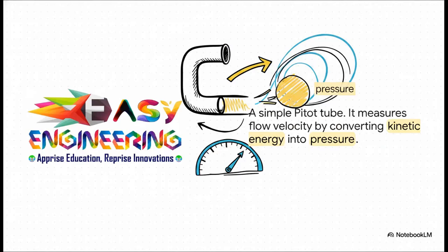And then there's the Pitot tube. It's just a simple little L-shaped tube that you point directly into the flow. The genius of this thing is its simplicity. It literally brings the fluid to a dead stop right at its opening. In that moment, all of the fluid's kinetic energy, its velocity head, gets converted into pressure. So by measuring that spike in pressure, you can work backward to figure out the original velocity. And yeah, this is exactly how airplanes measure their airspeed.